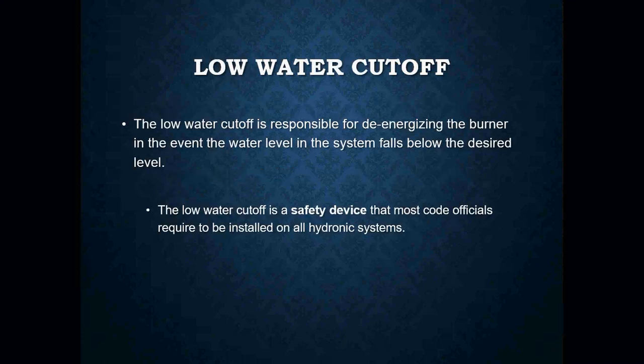The low water cutoff is responsible for de-energizing the burner in the event the water level in the system falls below a desired level. A low water cutoff is also a safety device that most code officials require to be installed on all hydronic systems. We cannot under any circumstances leave a low water cutoff jumped or bypassed in any way — that is illegal.